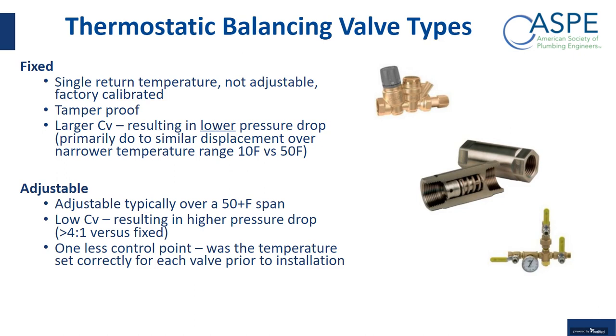Getting into the fixed versus the adjustable type of balancing valves out there, the fixed valve comes from the factory with a certain return temperature. It's not adjustable in the field. The actuators themselves can be changed out in the field, and very quickly. But as they come from the factory, they are set for a given return temperature. So sometimes people say they are tamper-proof because they're not adjustable.